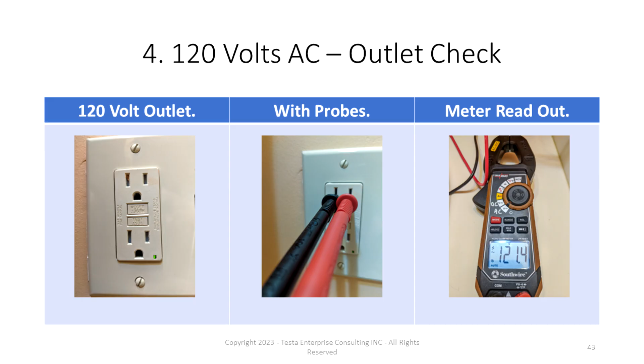To recap: the smaller slot on the right is red, the big one on the left, the neutral, goes to black — you should see 120 volts. If you move the black probe to ground, the half-moon shape on the bottom, you should still see 120 volts. But if you put the red probe in the left slot and the black one in the ground, you may see some stray voltage, but not 120 volts.